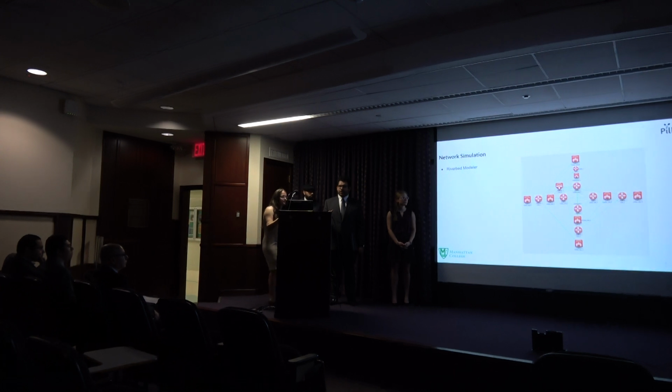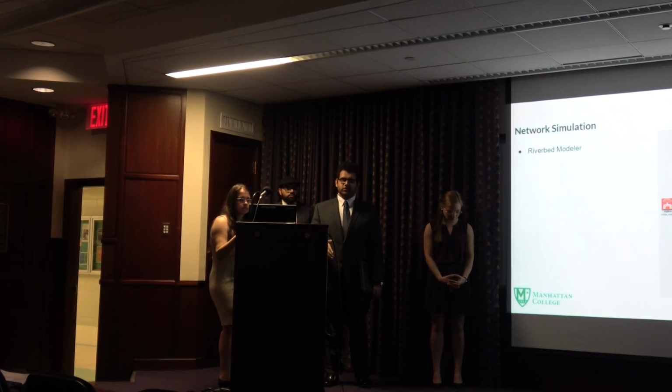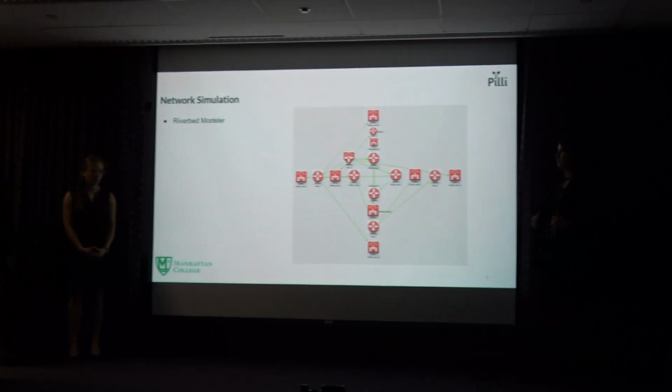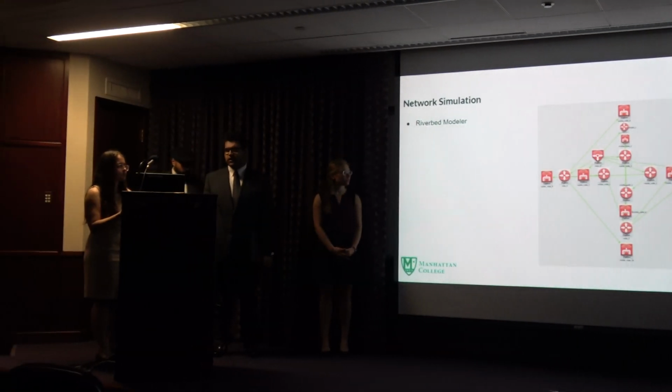However, because it is a mesh system, you can continue adding routers and end devices and extending the range. And you can theoretically add up to hundreds and thousands of end devices. What's really great about this system is it can split the load between different coordinators, different end devices, in more of a parallel sense, and it also has a self-healing function as opposed to a serial bus, where if it gets cut off at some point, the entire system goes down. We can actually fail one of these nodes within the software, and the other coordinators will take up the slack.